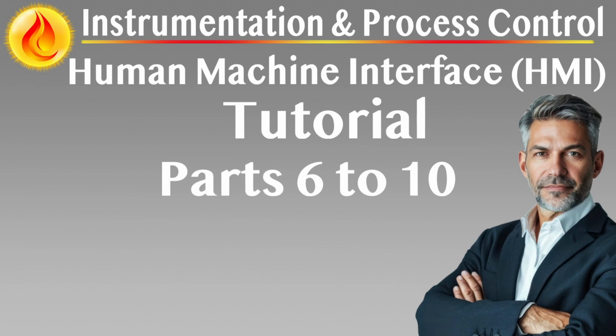Operator level, view and control permitted parameters, cannot alter configuration. Supervisor level, extended control functions, limited access to tuning and alarm parameters. Engineering level, full configuration access, including display editing and control logic changes.